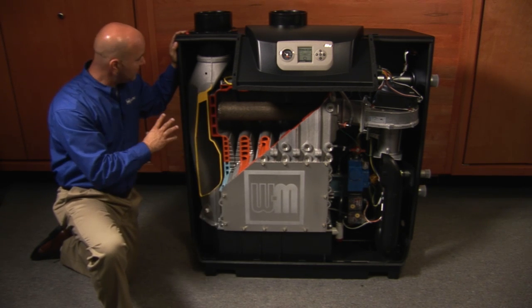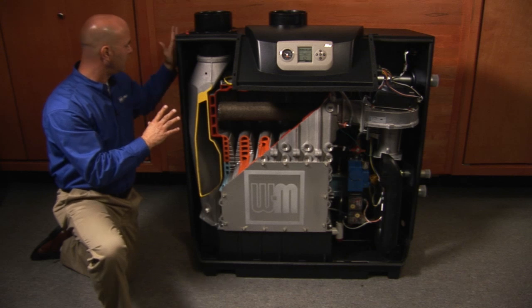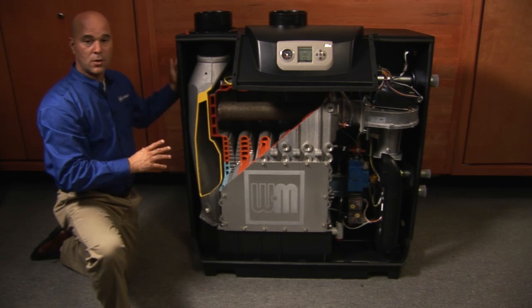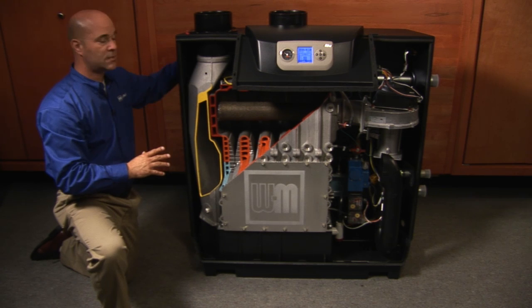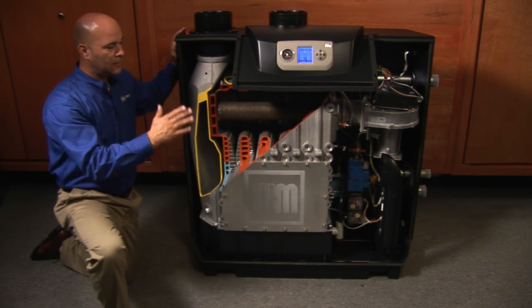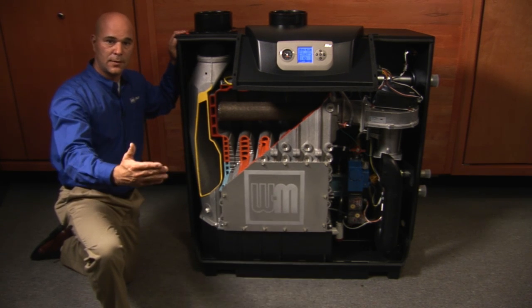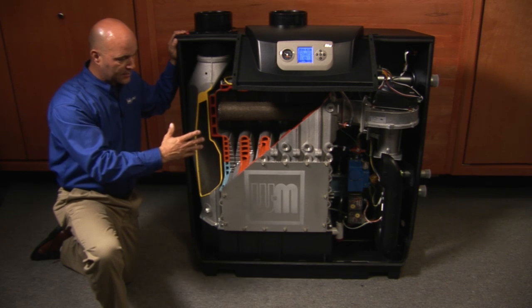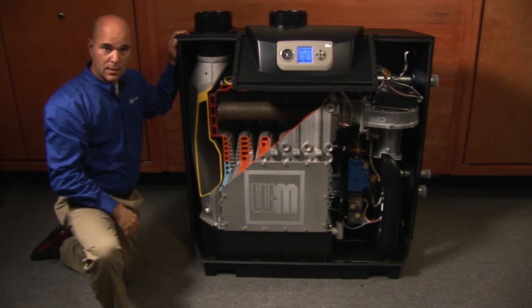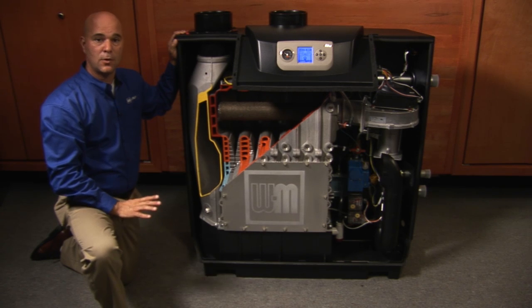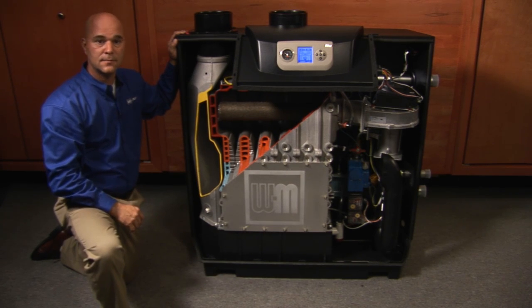That's a good view from this side of the boiler. One other thing to mention is zero clearance on this side of the boiler, zero clearance on the back of the boiler. The front of the boiler, you're going to leave yourself enough clearance so you can get in there and perform service on it. And on the right side of the boiler, you're going to want to leave yourself enough room. That's where all your piping and connections will take place.